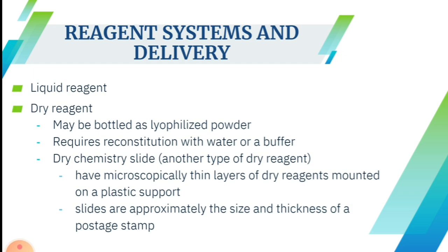Another means of preservation is to provide reagents in a dried tablet form and reconstitute them when the test is to be run. A third is to manufacture the reagent into stable components that will be combined at the moment of reaction. If this approach is used, the first component also may be used as a diluent for the sample. So the various manufacturers often use combinations of these reagent handling techniques.